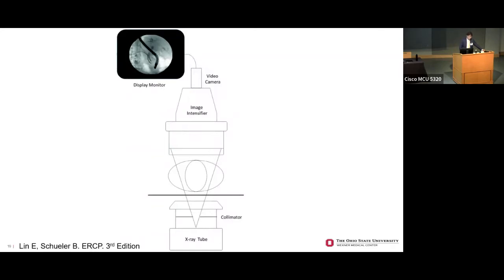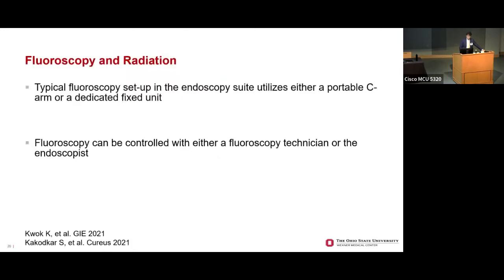And so the endoscopists themselves can actually adjust the blades of the collimator to basically narrow or widen their field of view or region of interest, if you will. And then most of us now have these image intensifiers or image displays, but basically they're digital now. So they capture the X-ray beams and they produce a digital image. And the nice thing about these things is that you can have a magnified image without actually increasing the amount of radiation used. So most endoscopy units will now have either a fixed unit or sometimes still a portable C-arm.